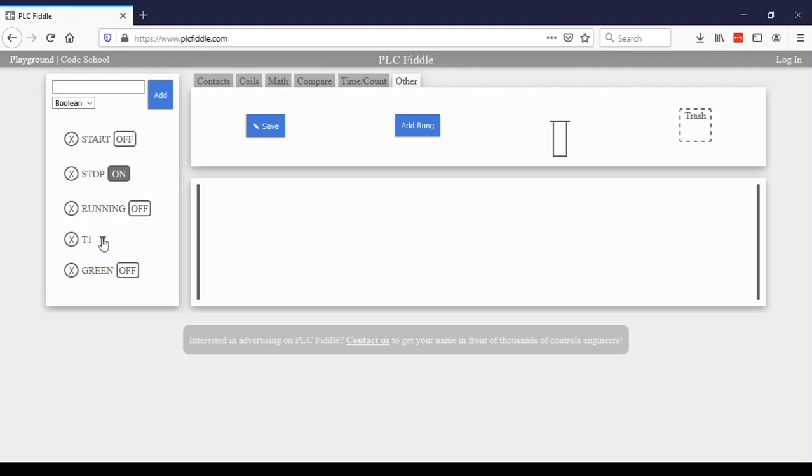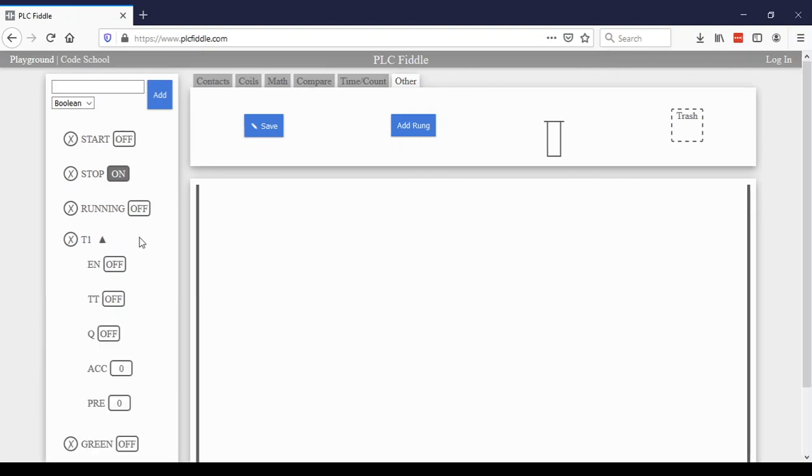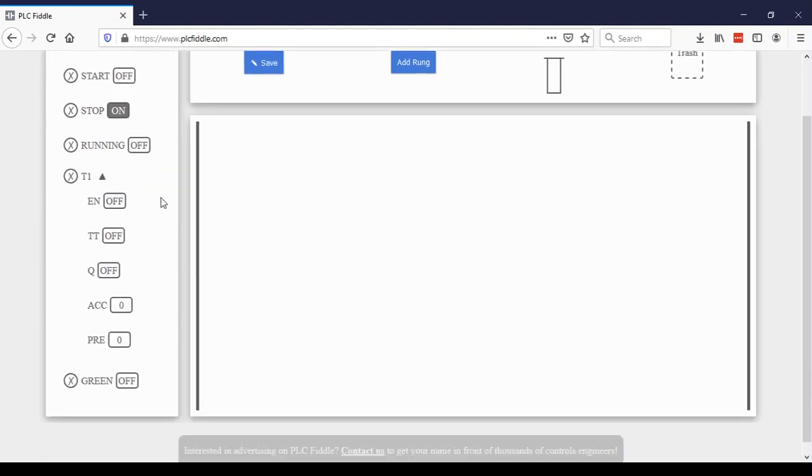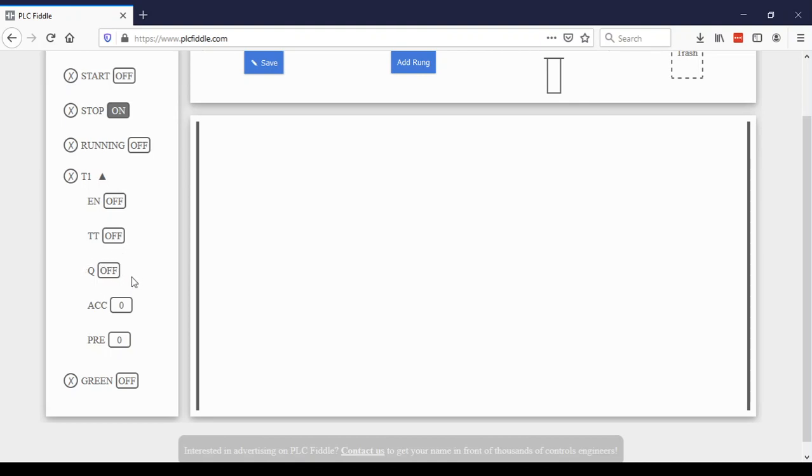T1, you can set up the timer one down here. So you can see the enable bit, timer timing and the Q bit are off. Notice the Q bit is what has been called in class the DN bit. So Q and DN are the same. It is the bit that will go high when the timer is done timing. The accumulator is the current value inside the timer. And the preset value is the value that we want the timer to say it's done once it reaches. So we're going to set that at five.